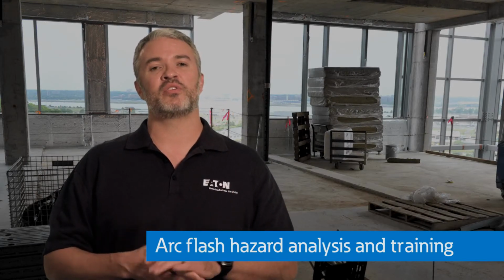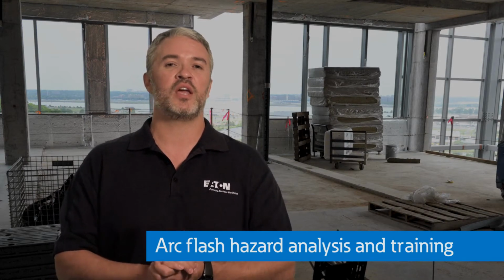If I was the electrical worker, wanting to know what codes and standards I should focus on, the first line of defense, from an electrical worker's perspective and from a contractor's perspective, is NFPA 70E. It's critical. It's not enforced by anybody outside of OSHA referencing it, but it's critical to electrical safety. And 70E pulls together the aspects of maintenance to make sure you install the products correctly per the NEC. So a focus on safety will go a long way from a reliability and from the electrical worker or electrical contractor's perspective. Consultants and engineering service providers offer arc flash hazard analysis and training, as well as advice on how to implement solutions that reduce arc flash levels.